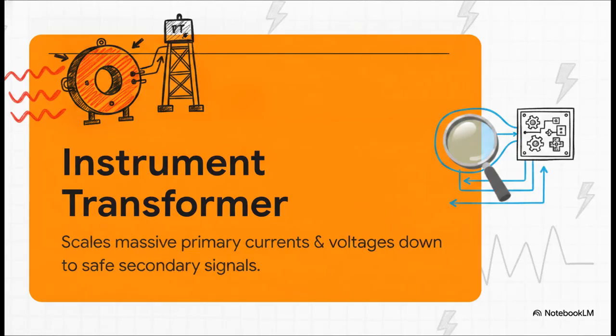Now, because the vast majority of substations out there are still rocking conventional analog current transformers, CTs, and voltage transformers, VTs, our relay has to interface seamlessly with that installed base. That is exactly what an instrument transformer does. It's a device purpose-built to scale down the massive primary currents and voltages from the yard into standardized, safe secondary signals that the relay can actually process.